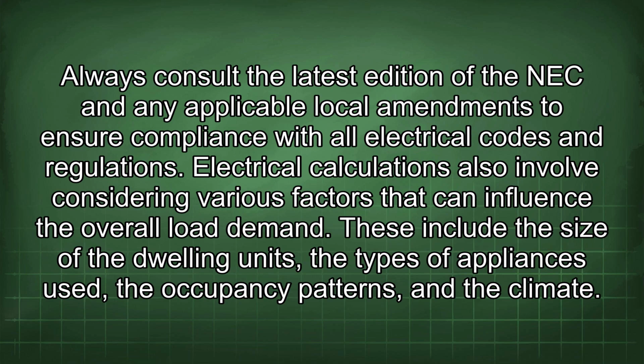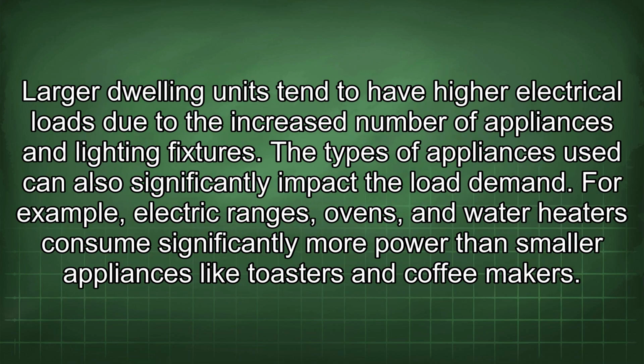and regulations. Electrical calculations also involve considering various factors that can influence the overall load demand. These include the size of the dwelling units, the types of appliances used, the occupancy patterns, and the climate. Larger dwelling units tend to have higher electrical loads due to the increased number of appliances and lighting fixtures. The types of appliances used can also significantly impact the load demand. For example, electric ranges, ovens, and water heaters consume significantly more power than smaller appliances like toasters and coffee makers.